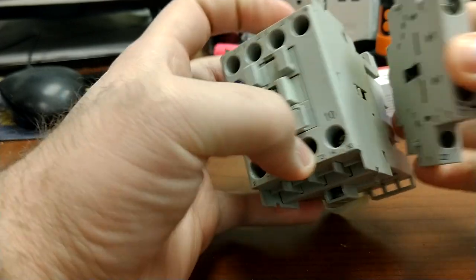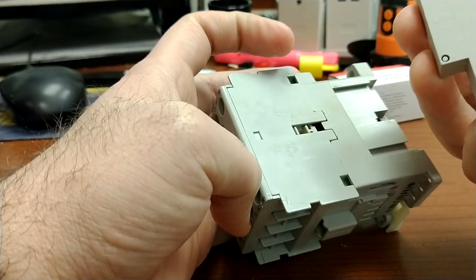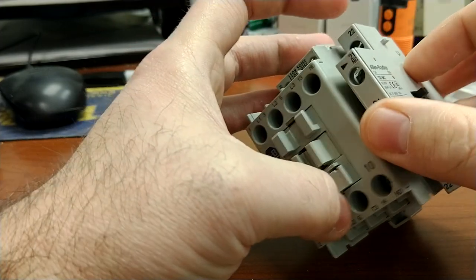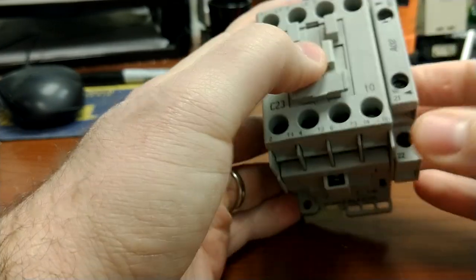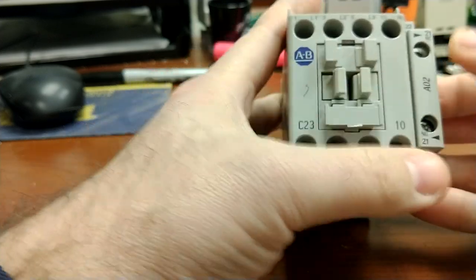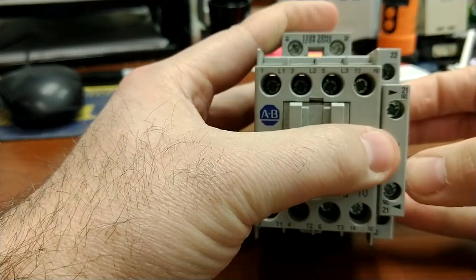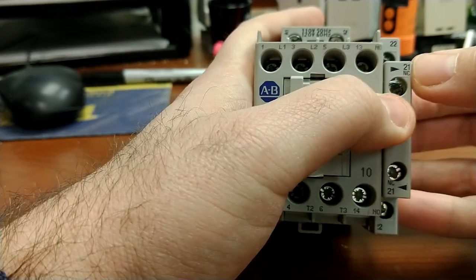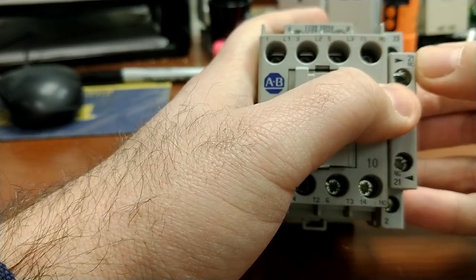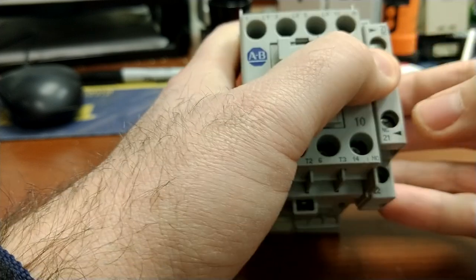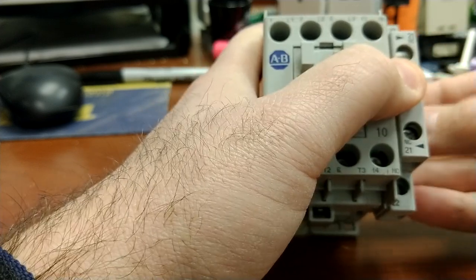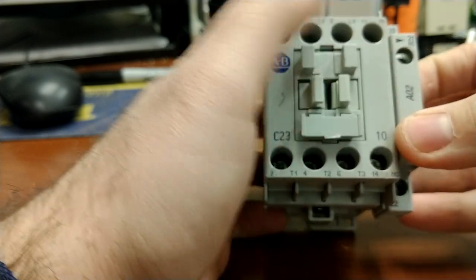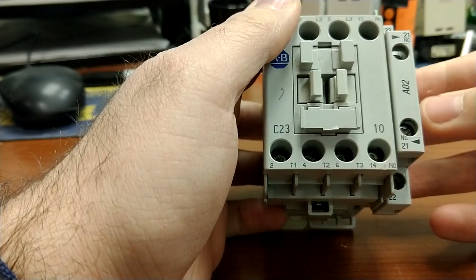So this is a broken one, so I can actually push back on this. But it sits right here, and you can see this moving part right here, that will go up and down as I manually engage the piston, or whatever you want to call it. But since this is Allen Bradley, it sits in, you can see the little dog ears right here that just sits in right here. And then if this engages, you can see that this will engage. Now, these are secondary contacts that you can actually do the same thing. And again, 2-1, that's your common, and this is your relay, 2-1, 2-2. See how that, and these are normally closed. So here I got normally open, here I got normally closed. So just be aware of those things.